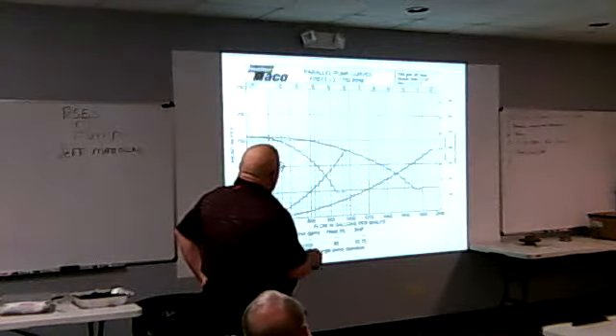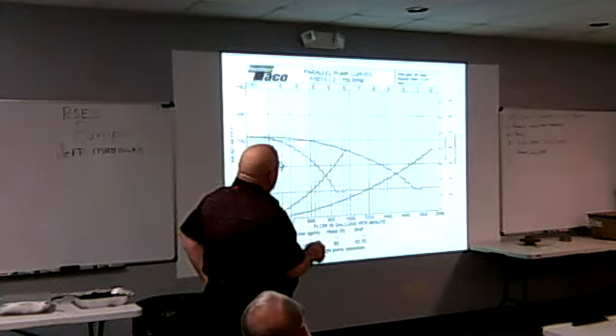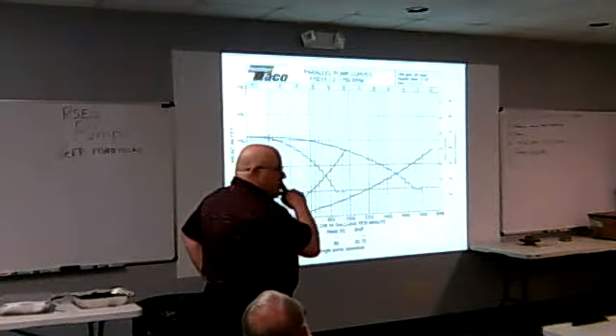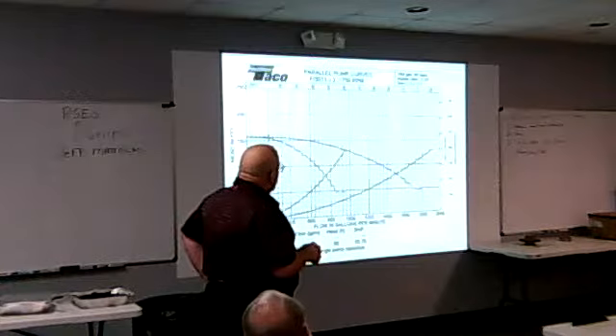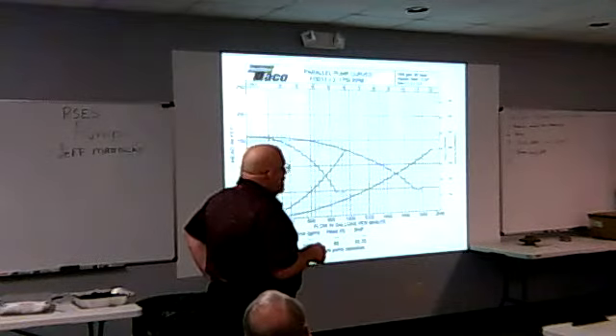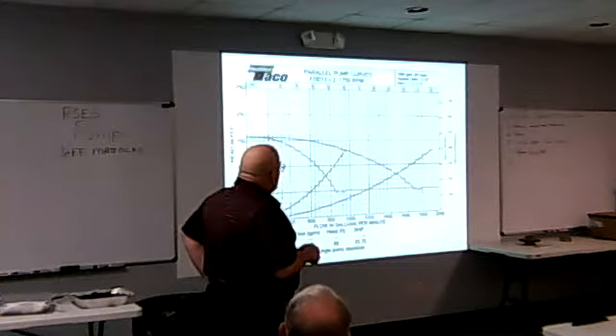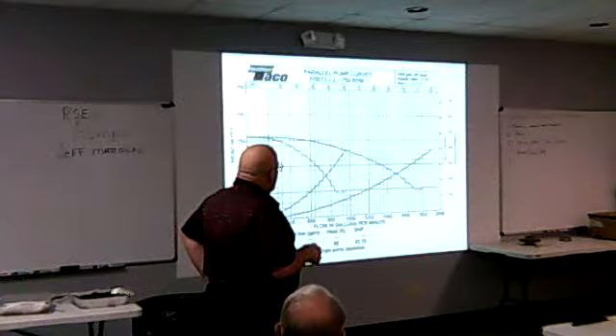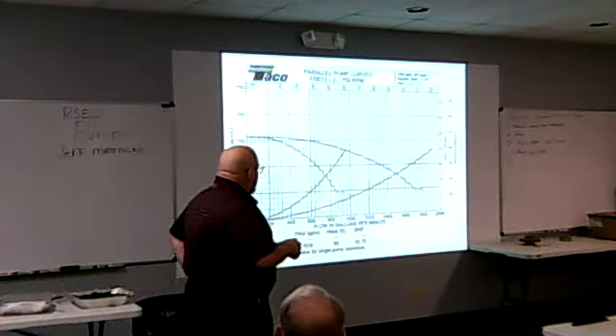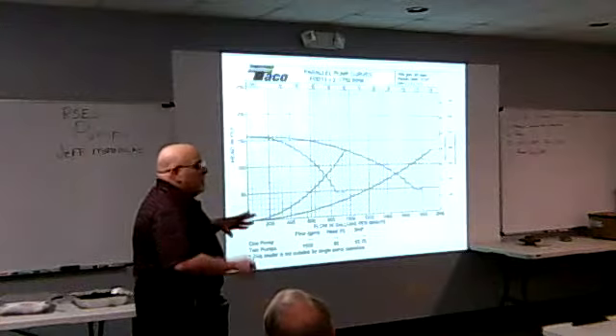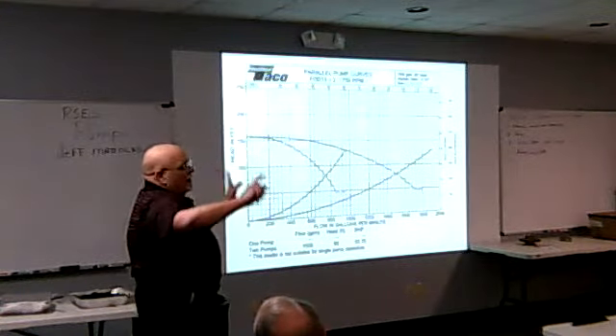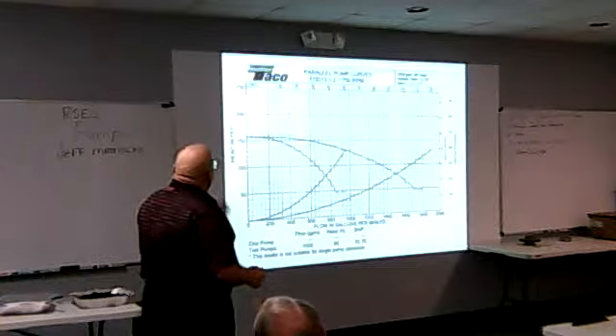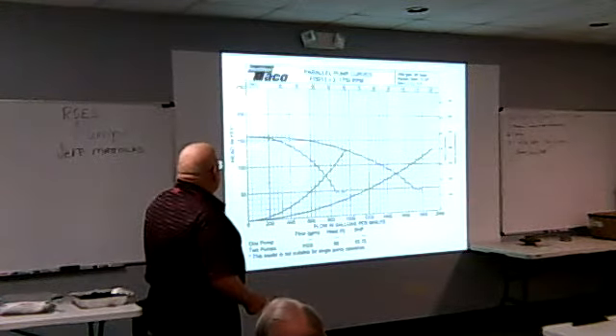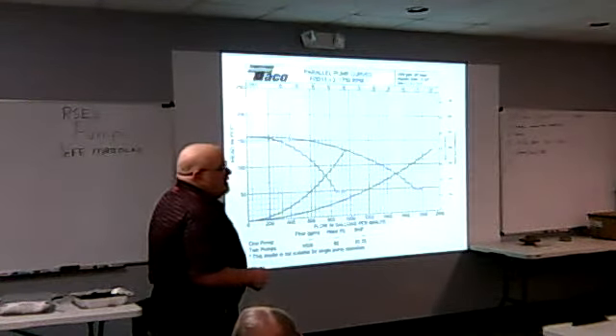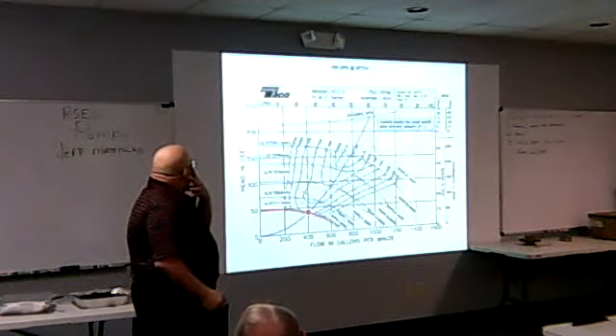Well, this is one pump individually. Yes. This is 2 pumps together. Can I put a line from P1, P2 on the left down to the other line, or does that not exist? I'm not quite following. If I want to extend that line, that doesn't exist below. No, that's my operating cutoff for that pump. There's no such thing. That pump is untested, doesn't exist. There are a lot of reasons, and that's one thing I forgot to discuss. Well, we're going to get into it. I didn't forget to discuss it. NPSH comes into play there. Let's not get into that.